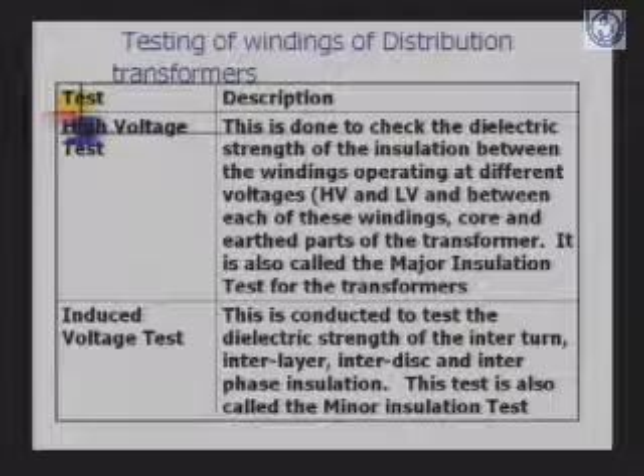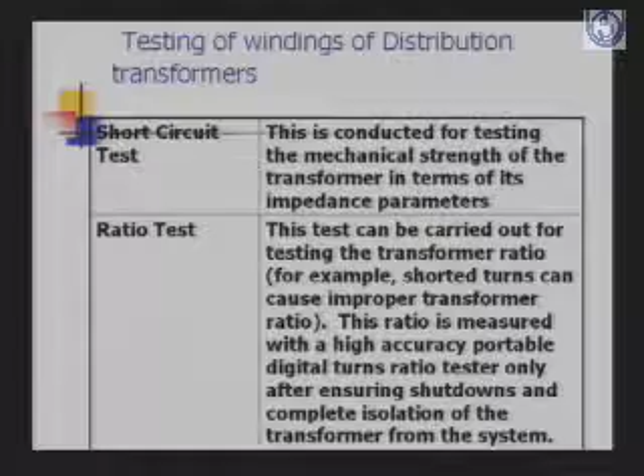Then we have the short circuit test. This is done for testing the mechanical strength of the transformer in terms of its impedance parameters. Like we said, if it has a higher impedance, then it has a higher short circuit withstand capacity. It is a destructive test generally, so it is a type test. Then the ratio test. This test can be carried out for testing of the transformer ratio. For example, shorted turns can cause improper transformer ratio. This ratio is measured with a high accuracy portable digital turns ratio tester only after ensuring shutdown and complete isolation of the transformer from the mains.